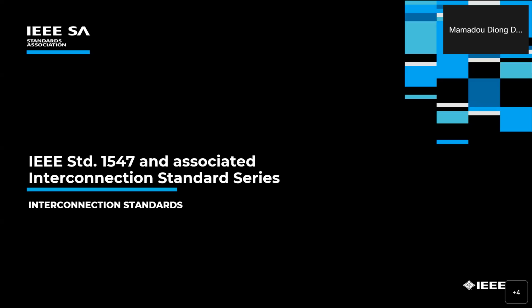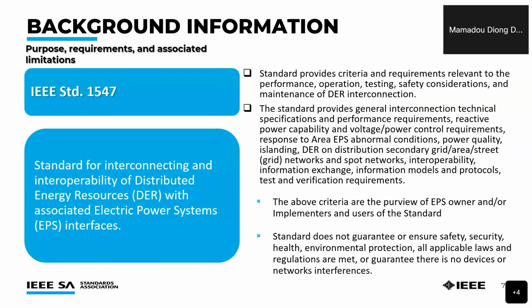With that in mind, I'm going to start the discussion on 1547 and the associated standards. Why 1547? It's a standard for interconnection and interoperability of distributed energy resources with the electric power system and interfaces. It provides criteria and requirements for interconnection of DER with the electric power system, including anything relevant to performance, operation, testing, safety consideration, and maintaining the DER interconnection to make sure it's actually helping the utility instead of hurting it. Just a few examples of items the standard handles.